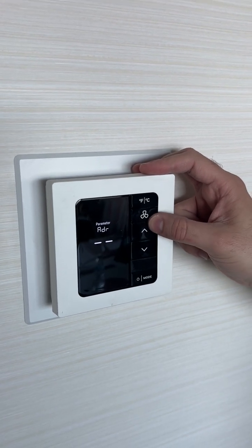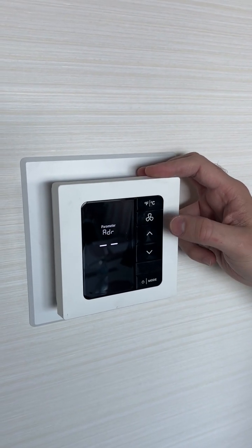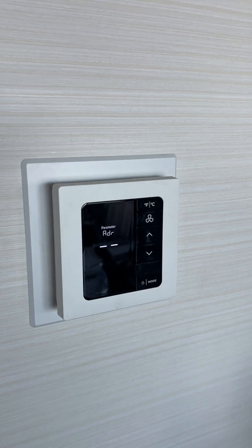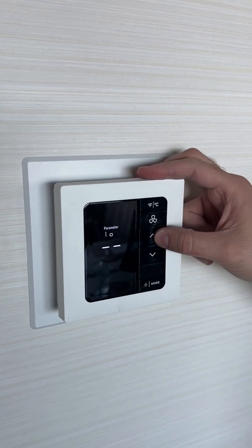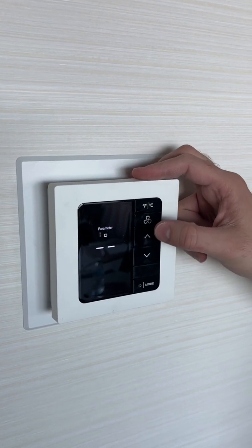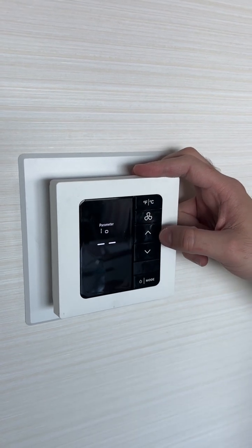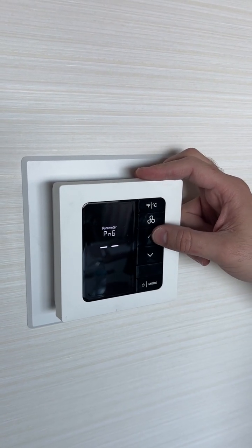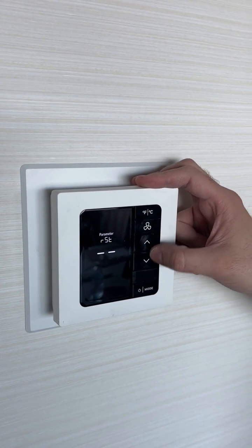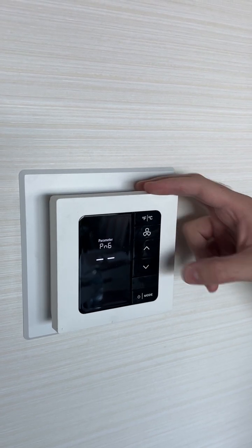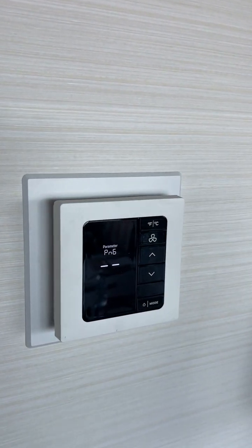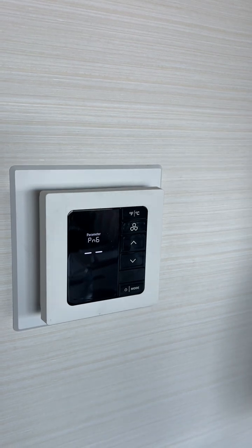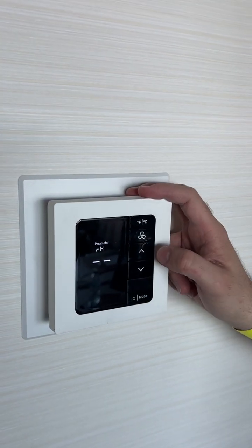What's one of those ADR ones again? Address. This is where we go to bind the door lock. Yep, that's right. And IO is for binding devices as well. That's where we go to bind the balcony sensor if we weren't using a laptop. And ping, what does ping do again? It just pings the devices in the room. You can put in a particular address and see if it's communicating. Okay, for troubleshooting.